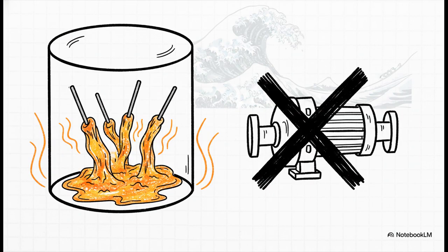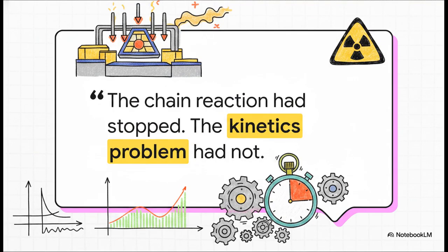And this isn't just theory. The 2011 Fukushima Daiichi disaster perfectly and tragically illustrates this exact physical reality. When the earthquake struck, the kinetics equations worked exactly as intended. The reactor shut down automatically, k fell below 1, everything worked, but the subsequent tsunami disabled the emergency diesel generators that were powering the coolant pumps. So while the active chain reaction was stopped, the total loss of those cooling systems allowed the relentless decay heat to literally melt the fuel over the coming days. It's exactly this engineering reality that led to modern reactor designs prioritizing passive cooling that doesn't need any pumps or power to operate.